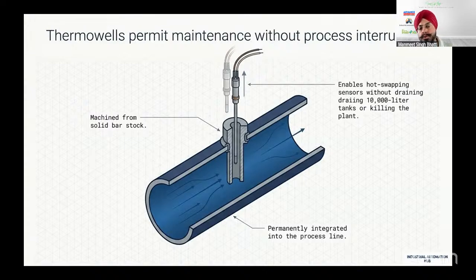Now, I will be answering your question a little later, but before that, I want to show you how thermowells are to be used along with the thermocouple. If you look at the picture, on the top side is the thermocouple. On the bottom, in the cross section of the pipe, you will find we have a machined bar. There is a rod of SS316 or 304, and we have machined it and inserted the thermocouple. We have done this because the thermocouple may or may not need removal from the process. Like you said rightly, we may have to calibrate it.